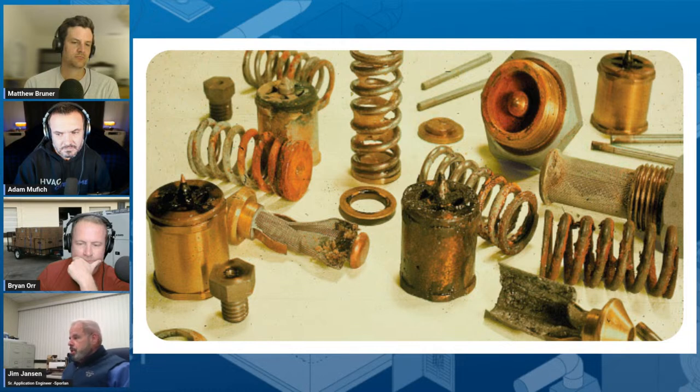We always like to say the only two things we want to see circulating in a refrigeration system are the intended refrigerant — not some concoction you've made by charging it with something else — and the appropriate lubricant. POE has some aggressive tendencies with respect to moisture and a scouring action. If you don't handle the lubricant properly, you can introduce moisture and have it deteriorate and cause problems. POE can separate into acid and moisture when it deteriorates in the right situation.